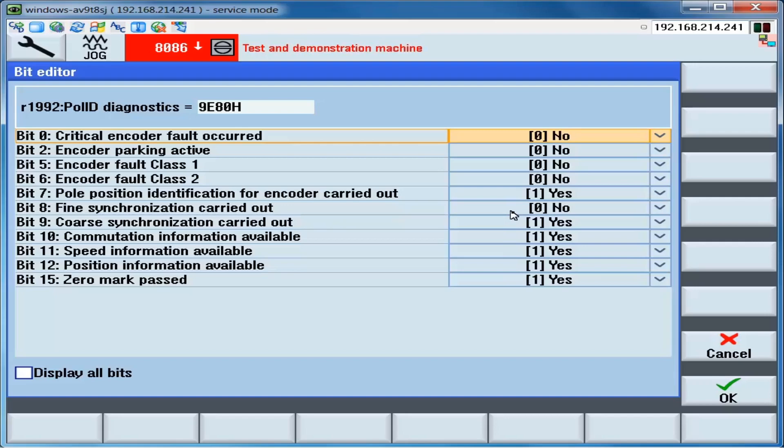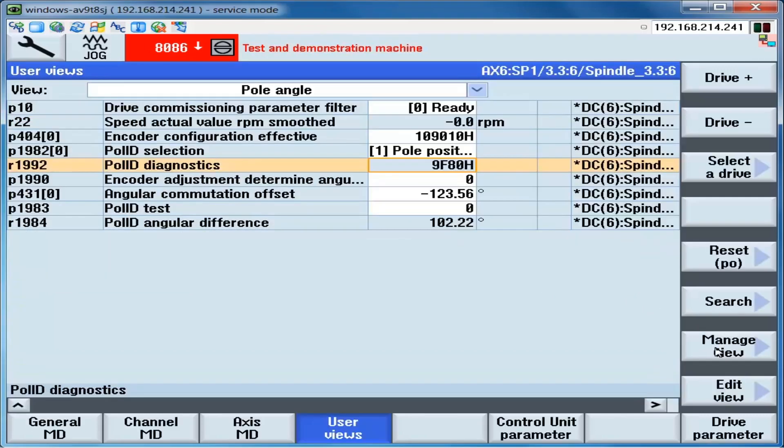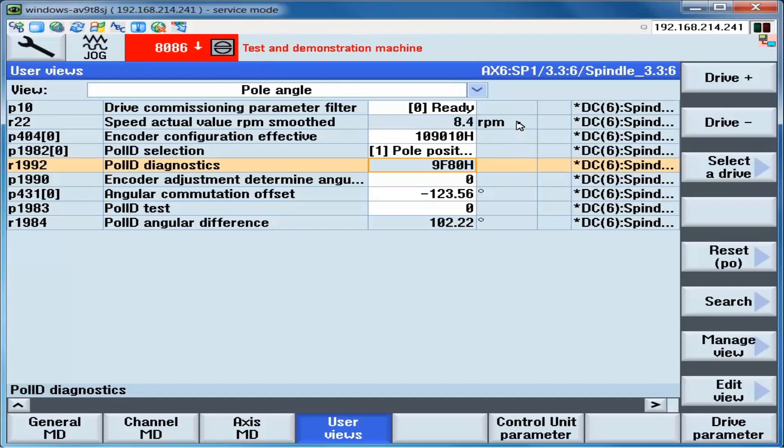Jogging the axis. And now we see that the zero mark was passed. And we are in fine synchronization. We should be able to jog the motor in both directions without any faults. Plus direction. Minus direction. And there are no faults.